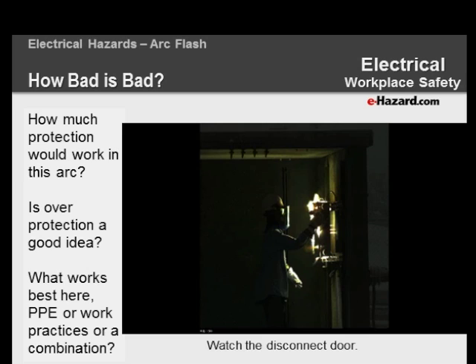How bad is bad? How much protection do you need to work in arc flash? This particular arc is going to blow off a door, hitting a worker in about 2 cycles, and in 6 cycles the worker is completely gone. The calculation on this kind of arc is 6 calories. By overprotecting, you don't do any good at all, because the worker is gone in about 2 cycles. What you really want to do in this situation is train workers on where to stand — not in front of the equipment. Standing to the side, what we call the left-hand rule or one-hand rule, is actually more protective than wearing PPE. If you stand to the side, your chance of being burned is extremely low, because most of the electromagnetic force pushes the energy directly out the door. You'll be much better protected by positioning yourself correctly than by relying on PPE alone.